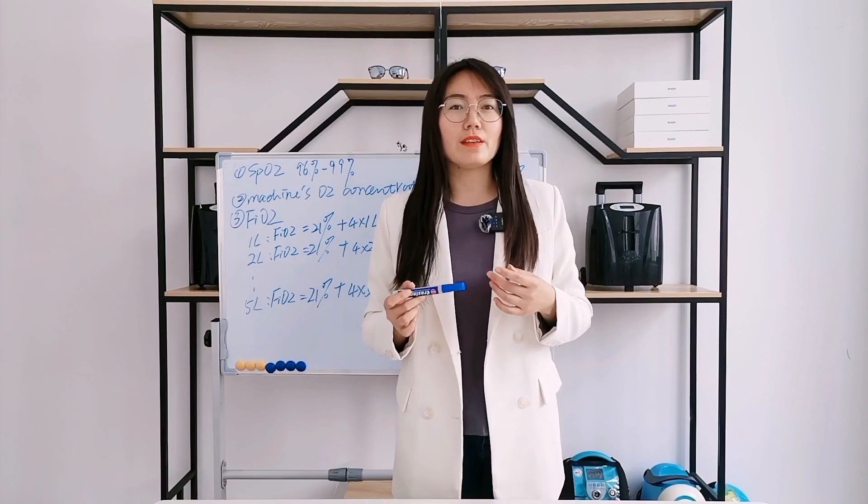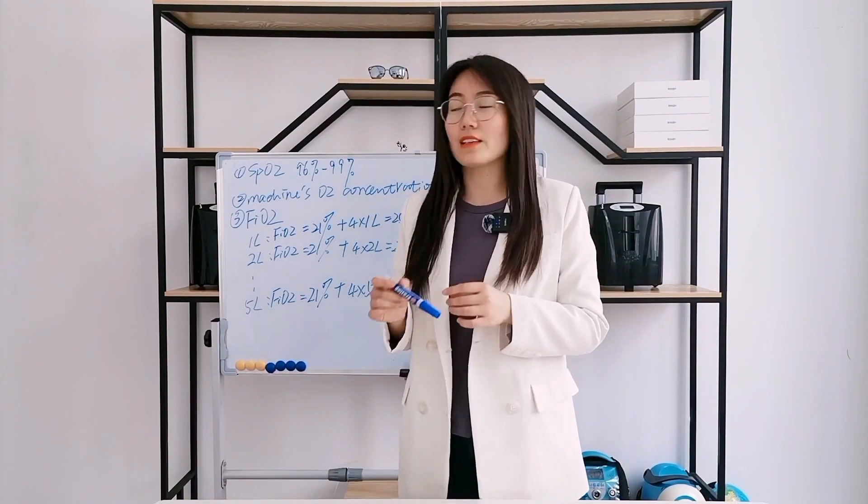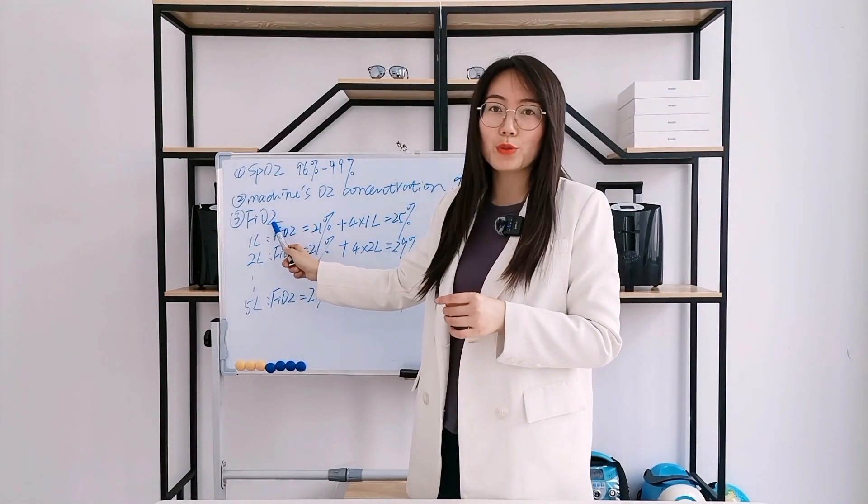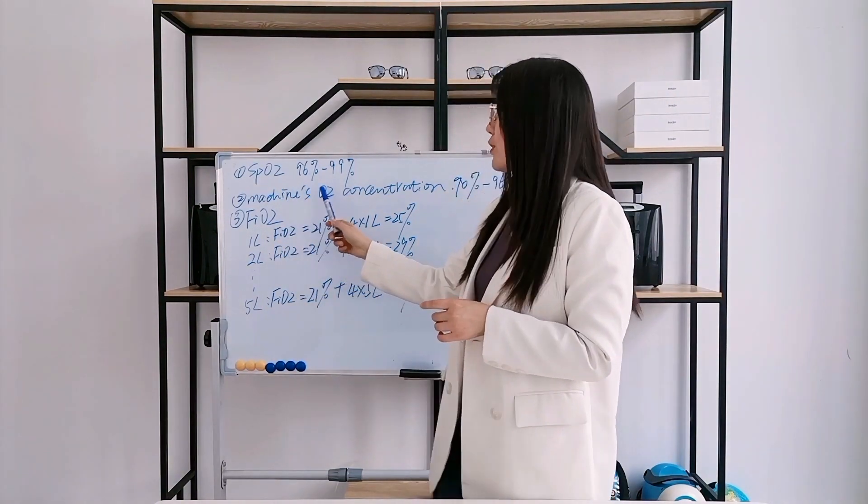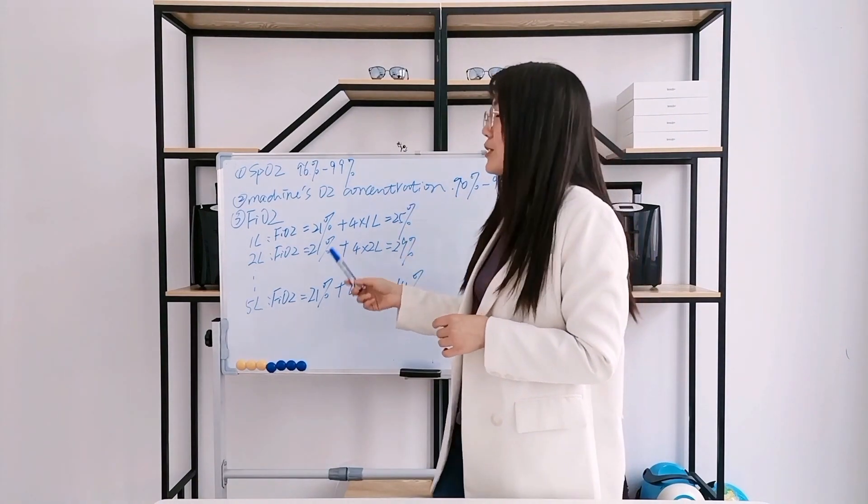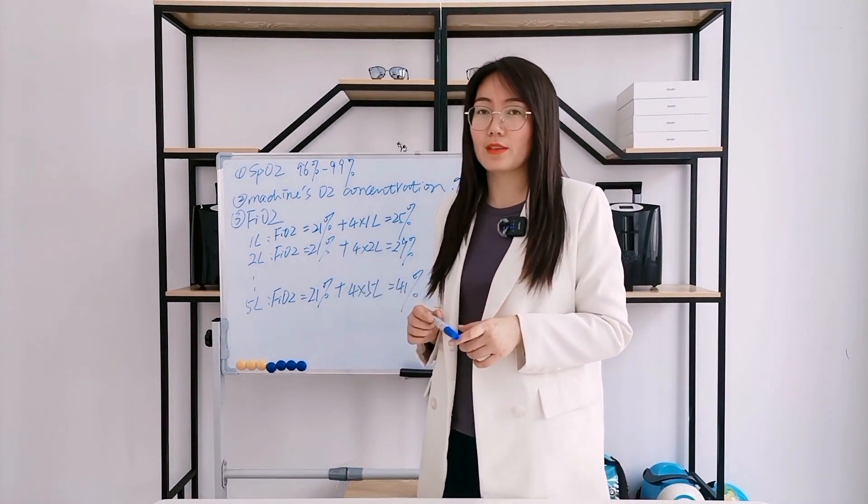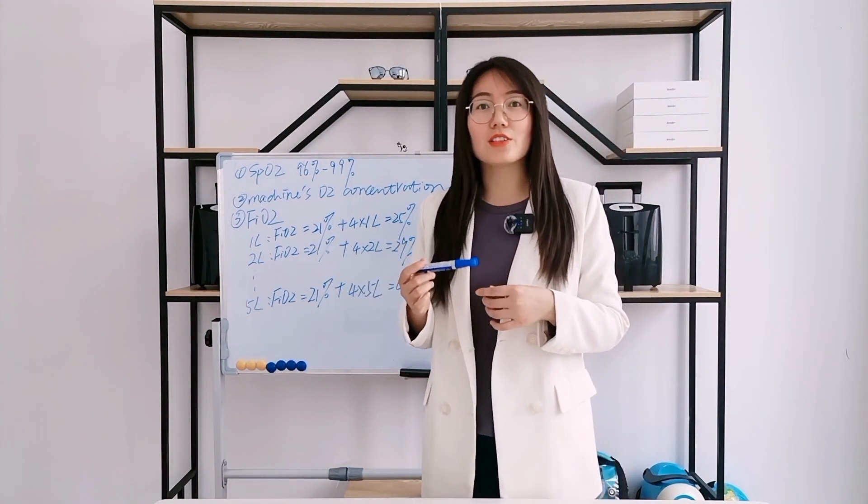In the case I mentioned at the beginning, this client said FiO2 is 40%. So he thought the machine's oxygen concentration should also be adjusted to 40%. That is a misunderstanding.